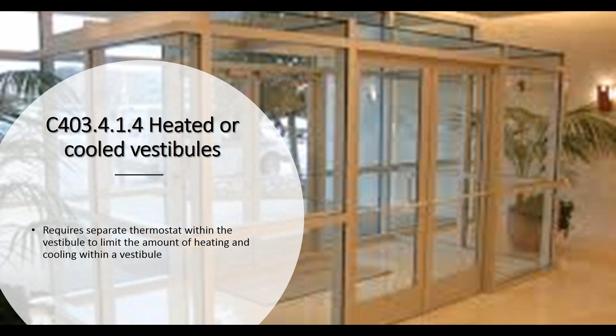A thermostat has to be provided in the vestibule that limits the temperature to not greater than 60 degrees for heating and cooling to not less than 85 degrees. I'm not cooling this or heating this to human comfort. I'm just tempering the air a little bit so it's not a drastic change. And that's what it's trying to do.